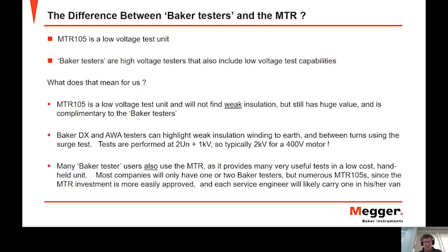The Baker DX and AWA testers can highlight weak insulation between the winding and earth or frame, and also between turns using the surge test. Tests are performed at twice the rated voltage of the motor plus 1000 volts, so typically 2 kV for a 400 volt motor. Baker testers are needed for when we're testing reliability, when we have critical motors that have to keep running. The MTR can't give you all of the answers for a critical motor because we're not using those higher voltage levels. So there could be a reasonable number of megohms at 1000 volts, which is the maximum voltage of the MTR, but at 1500 volts, winding to frame, there is a damaged area. The MTR won't find that, but the Baker testers will. So these are some of the differences between the units.